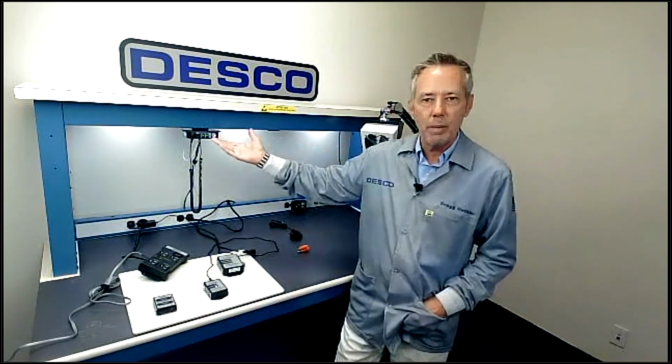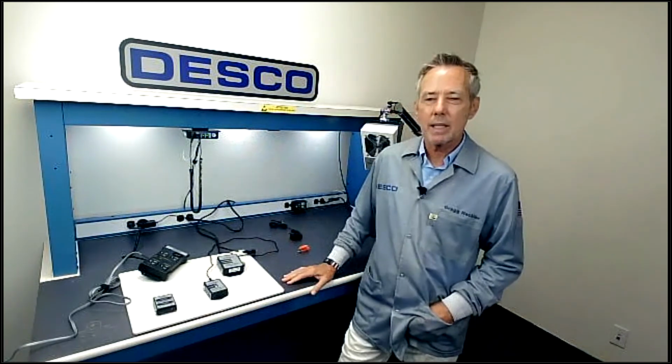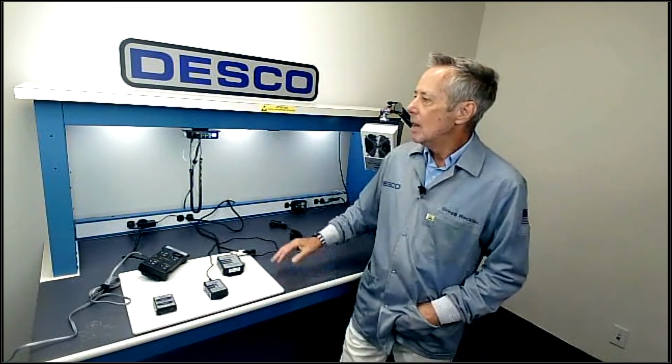Could be an ionizer, could be a monitor, whatever the electronics type item that we make is. You have to decide how often you want to calibrate. We recommend annually. For our monitors, we do have another convenience product. We manufacture a limit comparator for our Wave Distortion Technology, so you can purchase that and do your calibration in-house.